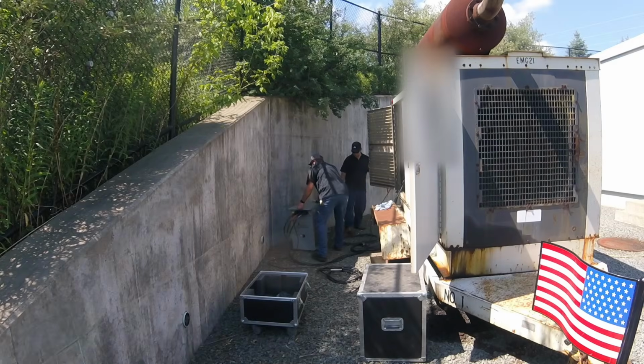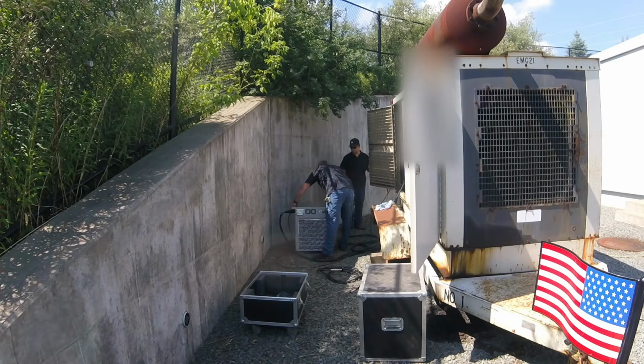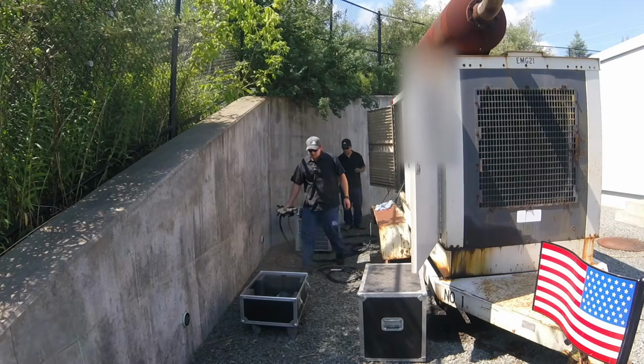So we've had that running for a little bit. The breaker seems to be holding that 100 kW load, no problem. The generator hardly grunted when we put it on there, so we're going to go grab our second load bank and hook that up and see if it likes a little more load, see what it does.